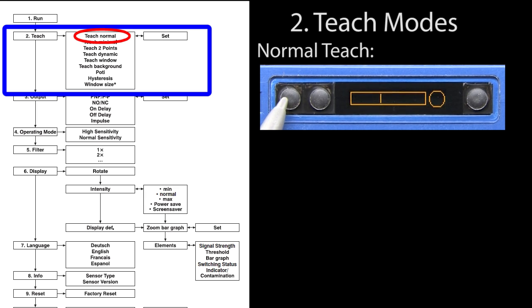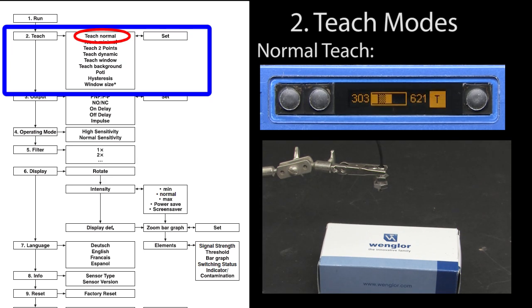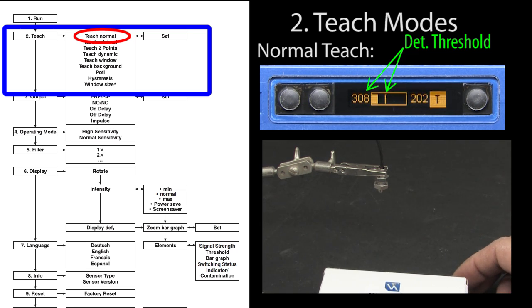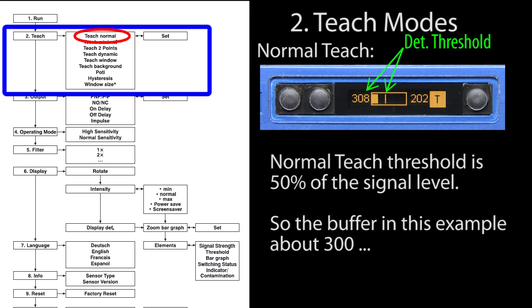For normal teach, press the enter button and down arrow to bring up the teach menu and press enter to drop down into the teach submenu. Normal teach is the first one, so hit enter. Place the object in front of the sensor. Notice that we are at a signal strength of around 600 and hit the T button. The display tells you the teach was successful. This vertical line here on the signal strength bar tells you where the cutoff is. We taught the sensor here at around 600, but any object that crosses in front of this sensor as low as around 300 will be detected. That's important to understand: teach automatically adds in a buffer so you don't need to worry about that.